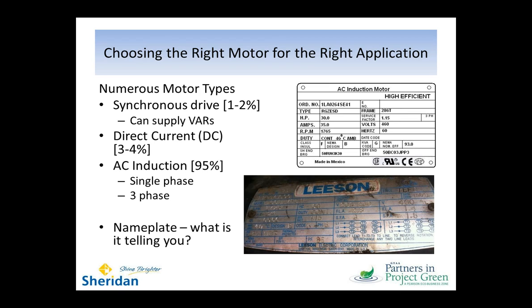That's also incidentally the generator of choice for an electric utility, because they're able to create real power and reactive power at the same time and balance their systems in terms of real power provided and reactive power. But synchronous motors are expensive, and there are a lot of options available these days for providing the same kinds of things that a synchronous motor can. So that's why we see such a limited rollout of those.